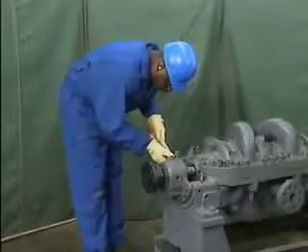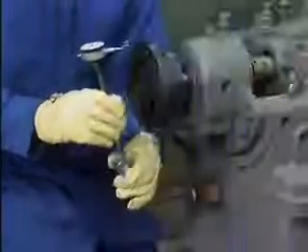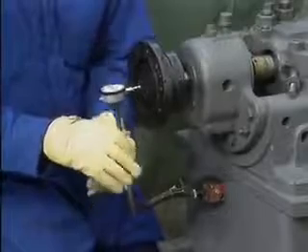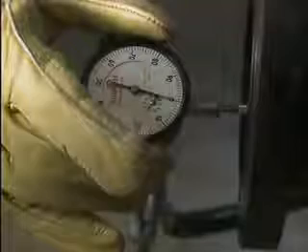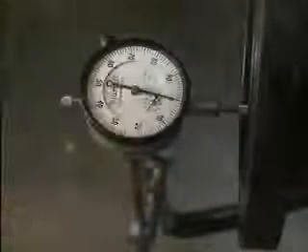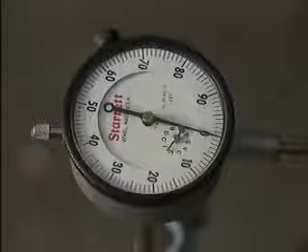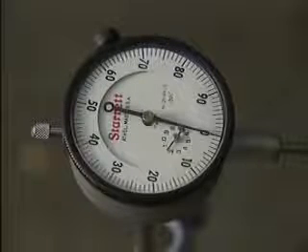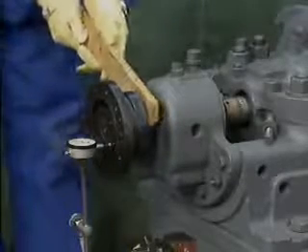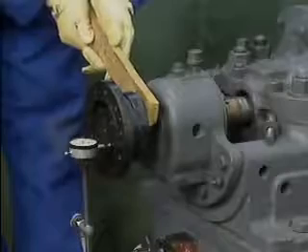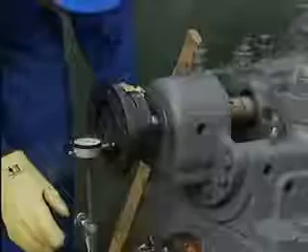To begin the procedure, the mechanic forces the pump shaft inward as far as it will go. Then he mounts a continuous type dial indicator so that its stem contacts the face of the hub. He then zeroes the dial indicator. Since the dial indicator stem was partially compressed during mounting, the small pointer indicates that nearly 200 mils of stem travel have occurred. With the dial indicator in place, the mechanic forces the shaft outward as far as it will go. Then he takes a reading from the dial indicator.